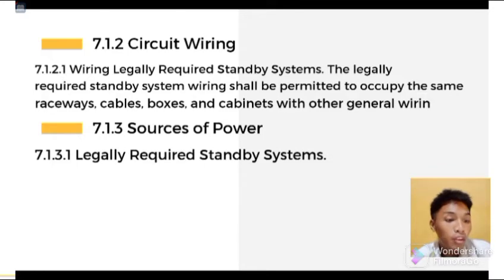Okay, so for the overcurrent protection, accessibility, the branch circuit overcurrent device in legally required standby circuits shall be accessible to authorized persons only. For ground fault protection of equipment, the alternate source for legally required standby systems shall not be required to have ground fault protection of equipment. For coordination, it shall be selectively coordinated with all supply side overcurrent protective devices.